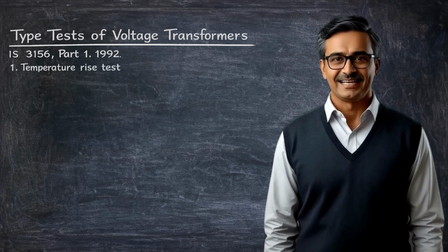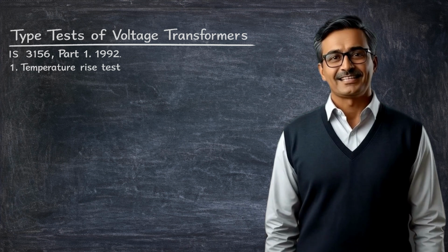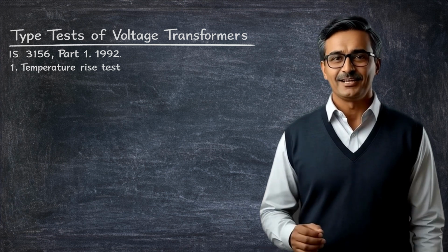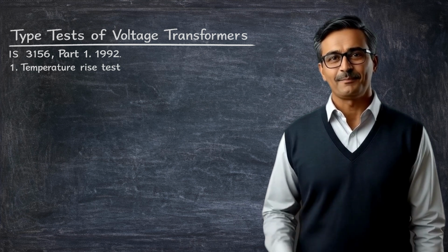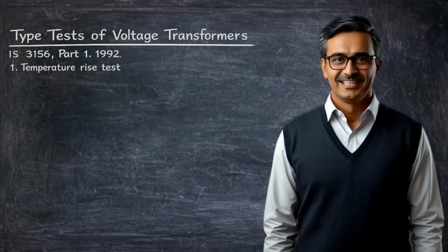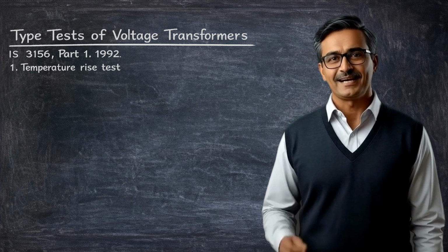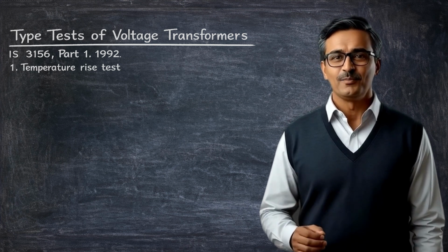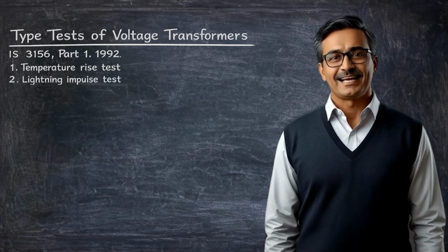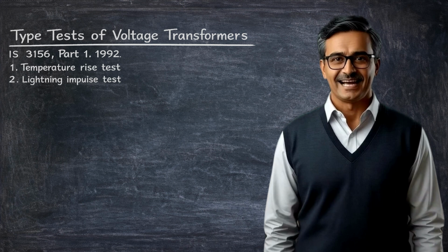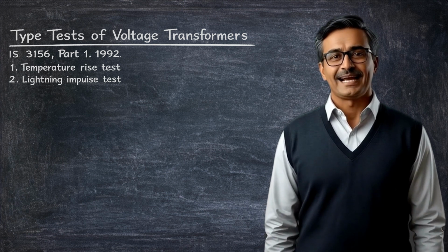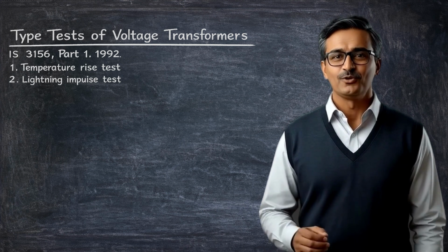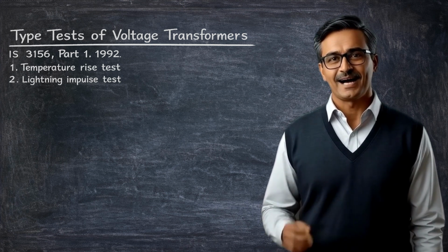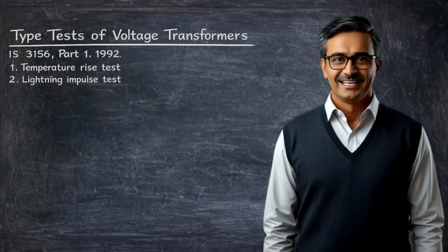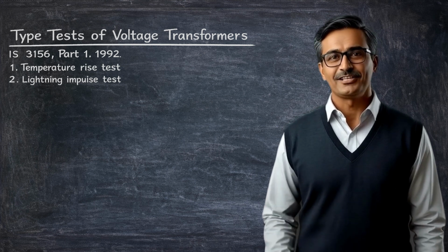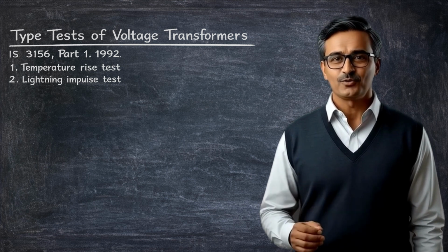The first type test is the temperature rise test. In this test, the transformer is operated under rated conditions and the temperature rise of different parts of the transformer is measured. This test ensures that the insulation and materials can withstand the heat generated during normal operation. The second type test is the lightning impulse test. This test is carried out for voltage transformers installed in electrically exposed locations such as outdoor substations. In this test, a high voltage impulse wave simulating lightning surges is applied to check the insulation strength of the transformer against lightning overvoltages.